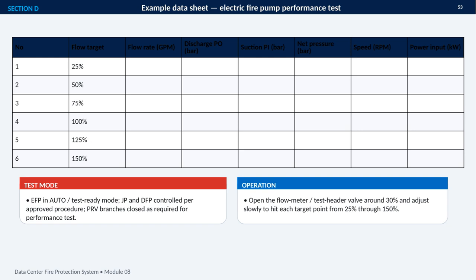For operation, the flow meter or test header valve is opened to approximately 30%, then adjusted slowly. The goal is to reach each target point in sequence, from 25% to 150%, while recording the corresponding readings in the table. The key requirement is controlled, steady adjustment at every test point, so the results are reliable and comparable.